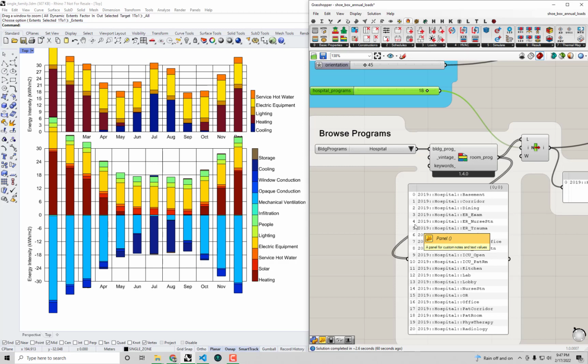In the office, you might say, all right, let's make the windows a little bit smaller. Let's use some better windows so that we mitigate the conduction and solar gain from those windows. But in the patient room, the solar term is so incredibly small in the grand scheme of things. So if we're going to target the energy use of a patient room, we're best off really trying to reduce this mechanical ventilation one way or another. Probably the best strategy for that would be something like heat recovery, which you've heard me mention in earlier videos.